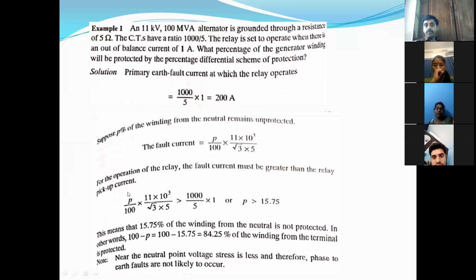Now if this fault current is greater than 200 amperes, the relay will operate. For the operation of the relay, the fault current must be greater than the relay pickup current. So the fault current from the formula should be greater than this primary current. Then P should be greater than 15.75. What is P? The percentage of the winding unprotected. Therefore, 15.75% of the winding is unprotected from the neutral. So what is the percentage of the winding protected? 100 minus P, that means 84.25% of the winding is protected by this scheme. Understand?